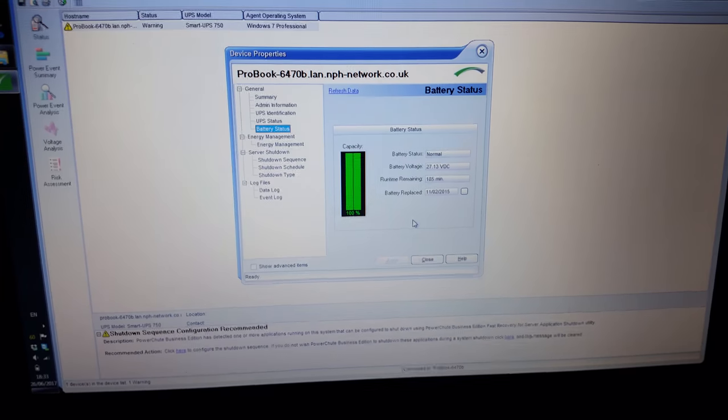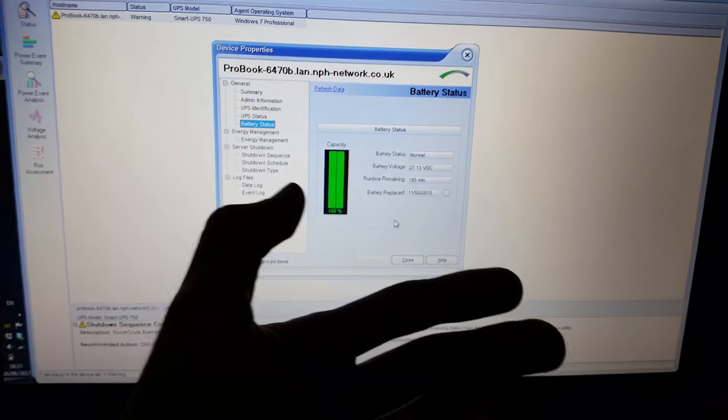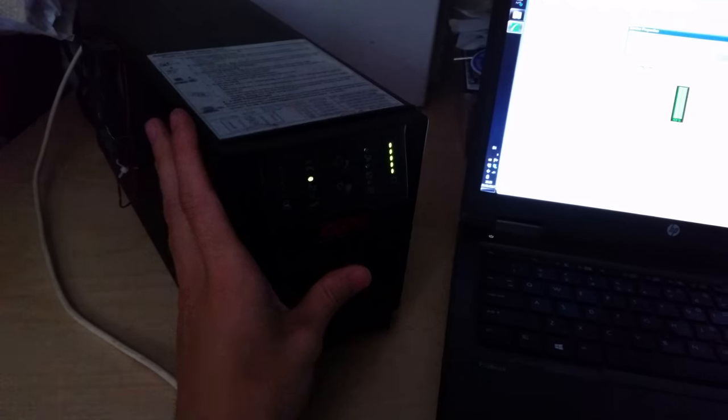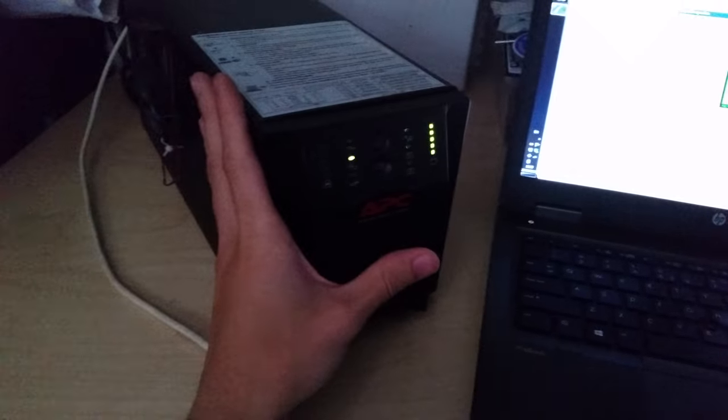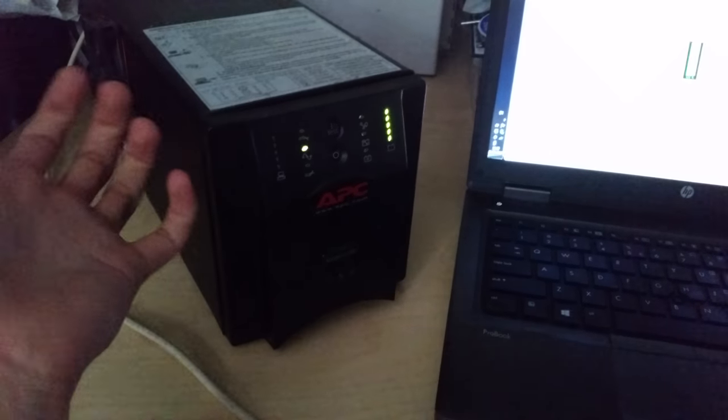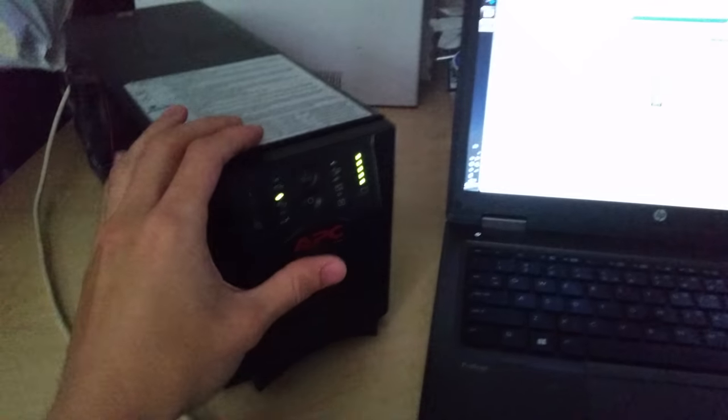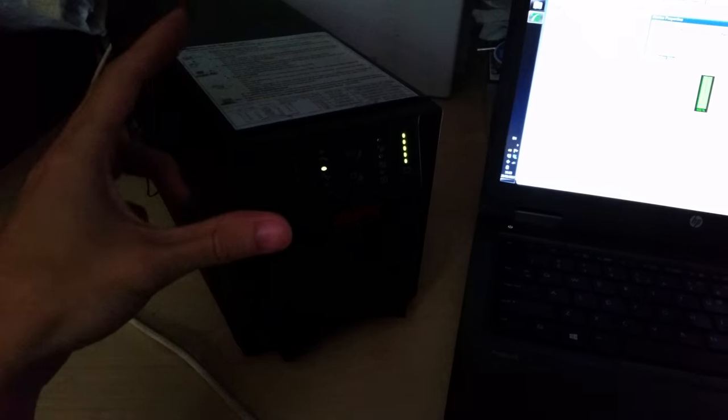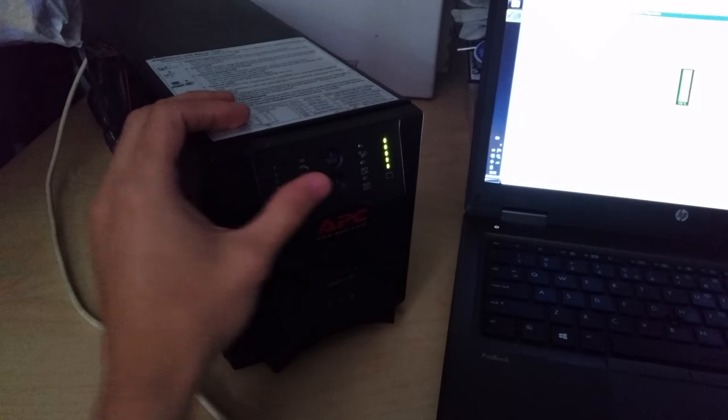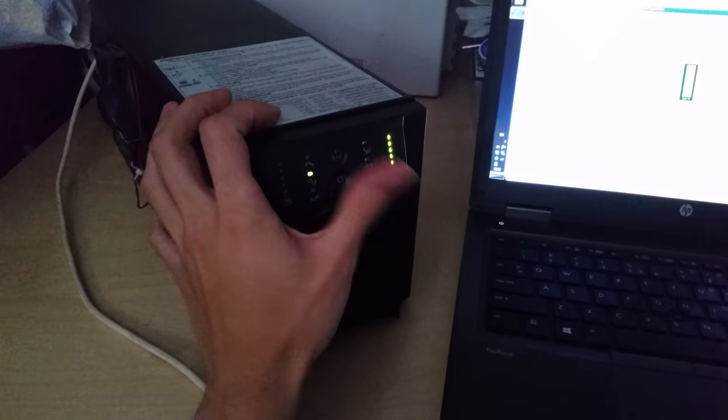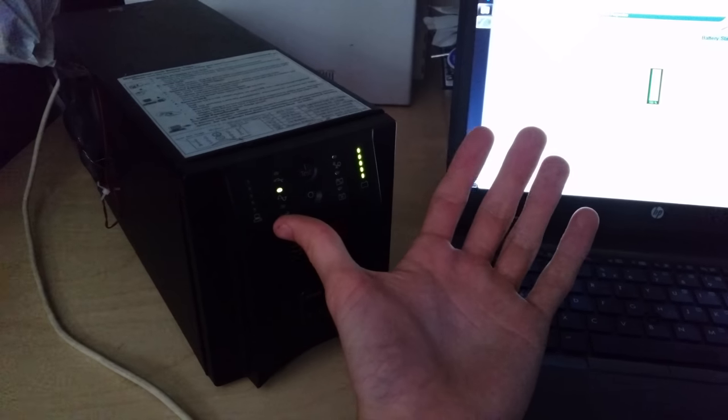I think it might be worth running this thing down with a load on it completely flat and recalibrating the batteries. Now, how you recalibrate them is you get something like a light, halogen lights lots of people use for them, that's probably a bit much for this, but something like normal light bulbs and put them on it and just run it down from a full charge all the way down to completely flat where it switches itself off. That's how these units calibrate. So I'll go and find a light bulb and some things to run off it that'll put a constant load on it.